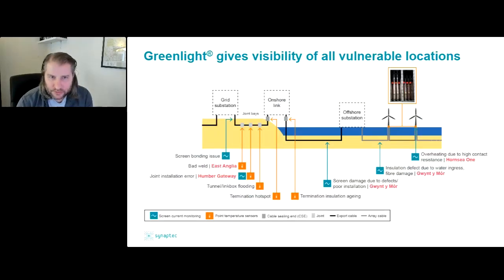So this slide shows how and where we find issues in cable systems. Failures in cables, as I said already, are commonly happening at joints and terminations, which are not adequately monitored by conventional monitoring systems, or those systems are simply too expensive to deploy at scale. As Saul introduced earlier, we deploy passive point sensors that can measure phase current, screen currents, and temperature at these critical locations. That's not an exhaustive list, but that's typically what's applicable here.